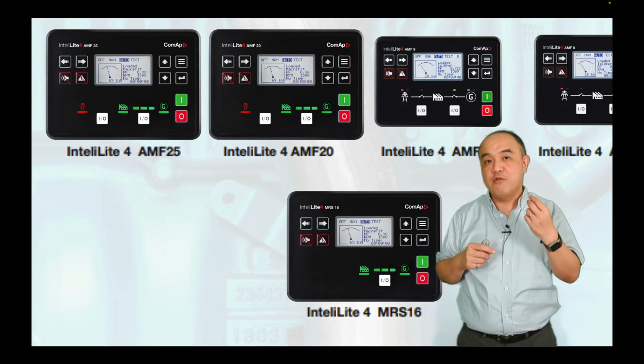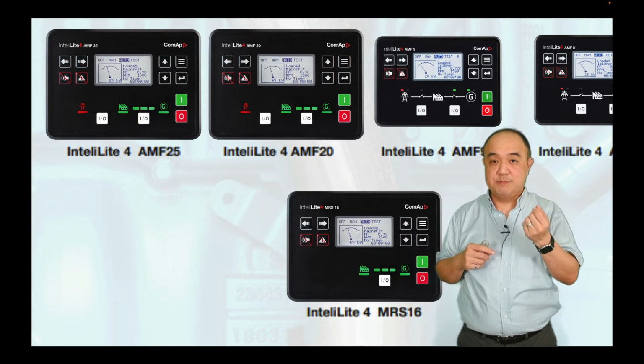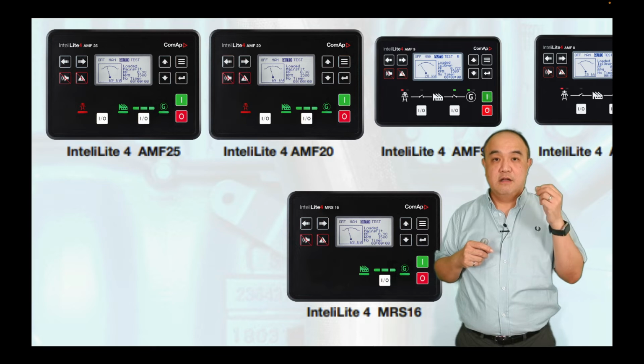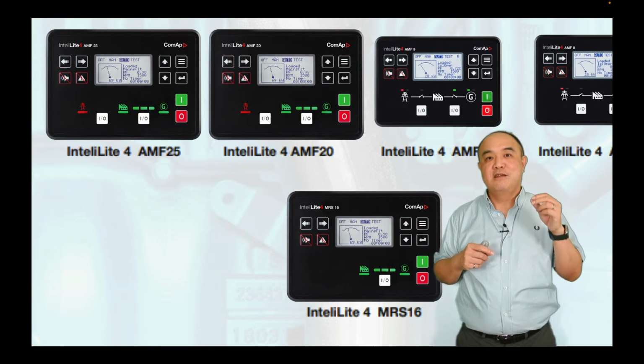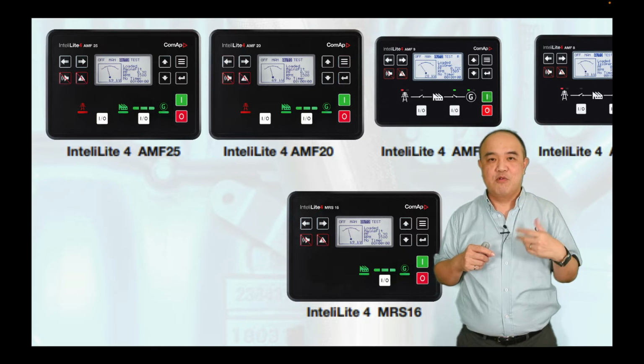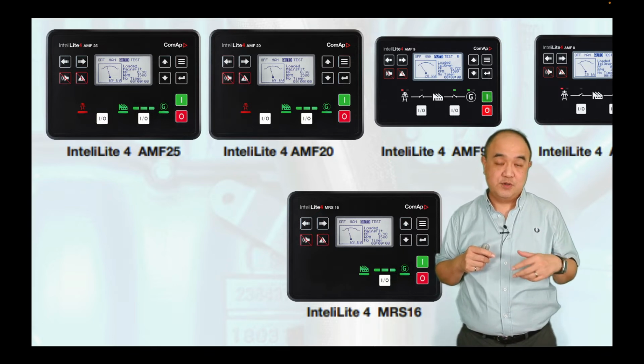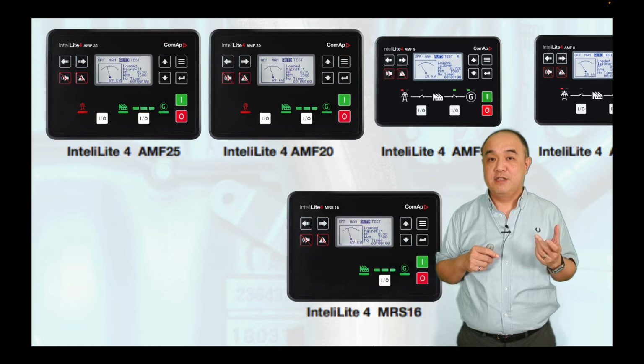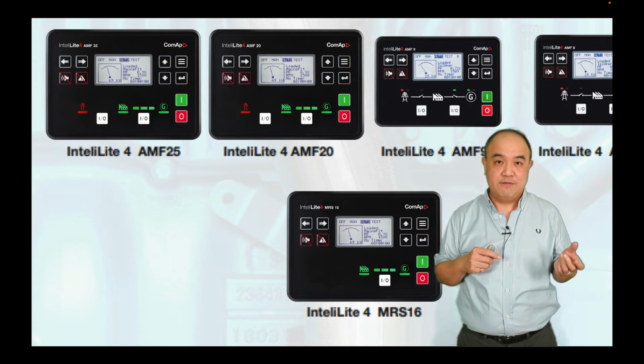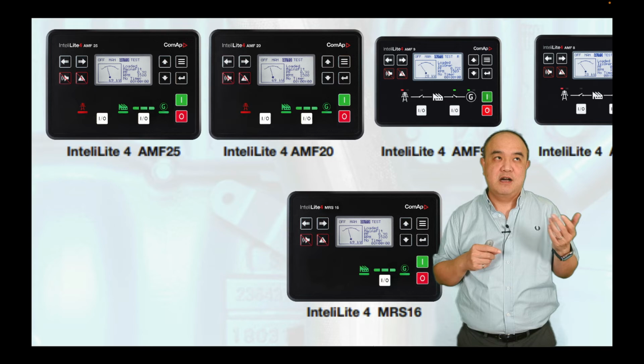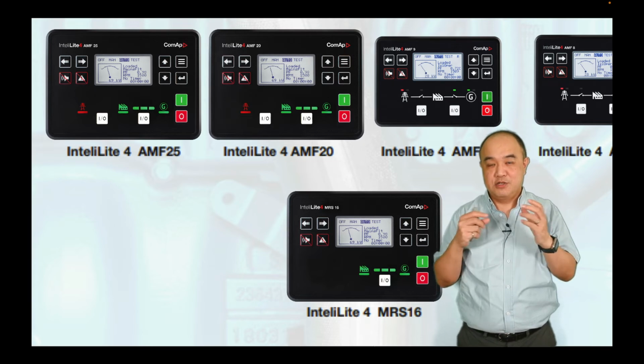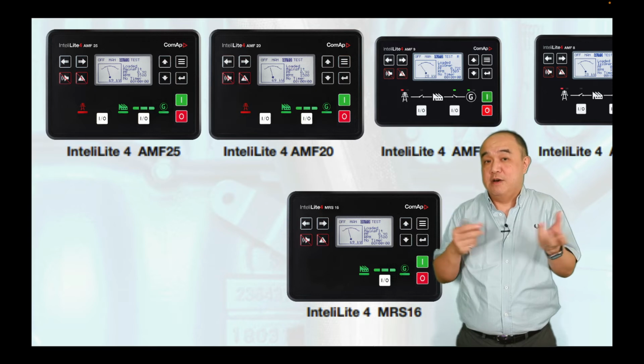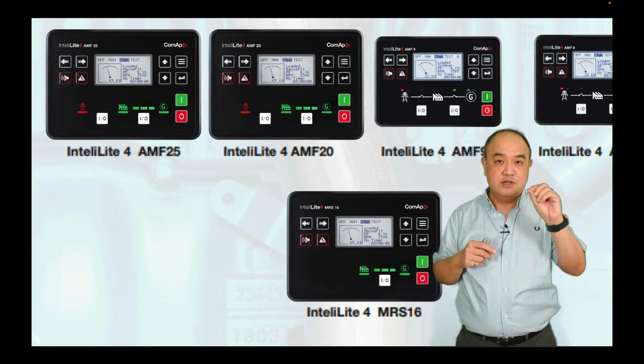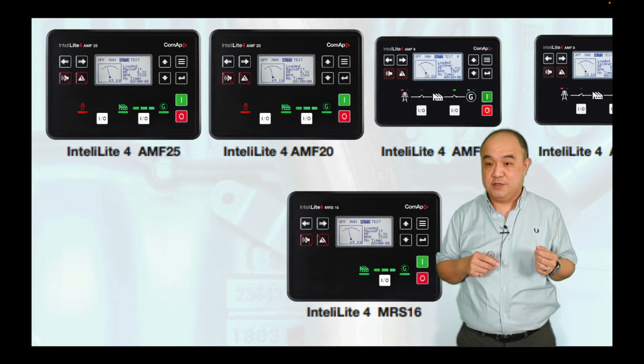And you can also program the controller itself using a USB stick with the user ID and password, user ID and PIN, for InteliLite 4. You stick in the USB, and you can reprogram the unit without having to use a computer. So you can upgrade the firmware, and you can change settings if you have the UID and PIN. This also is very convenient for trying to help the customers to resolve some issues, some settings they have. Maybe they set something wrong. For instance, if some mains protection limits are set a bit too tight, they want to change it, but they don't know how to change it themselves, you can send them a file, and they can use a USB to change it.